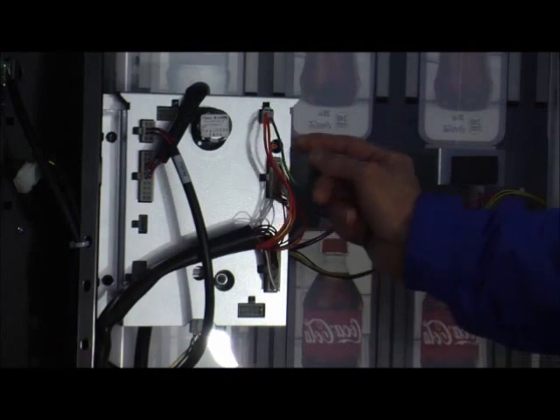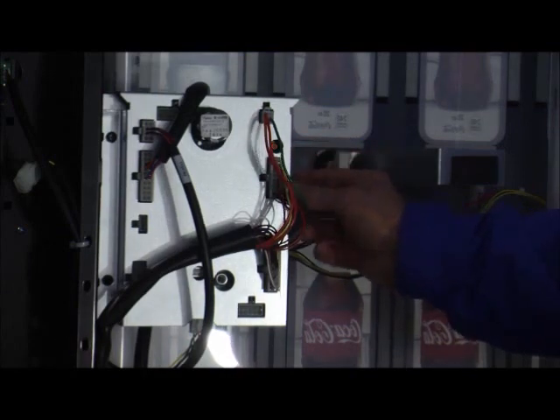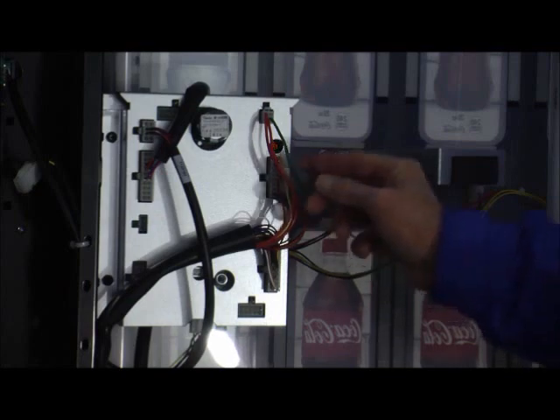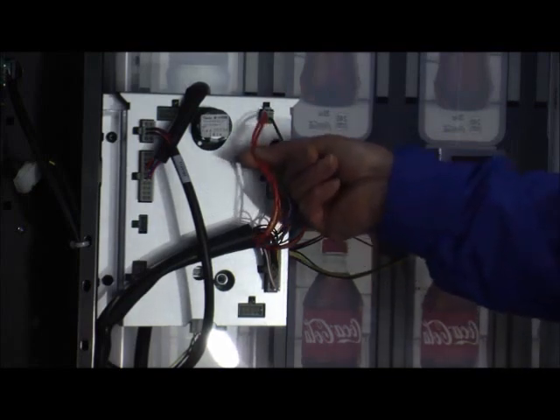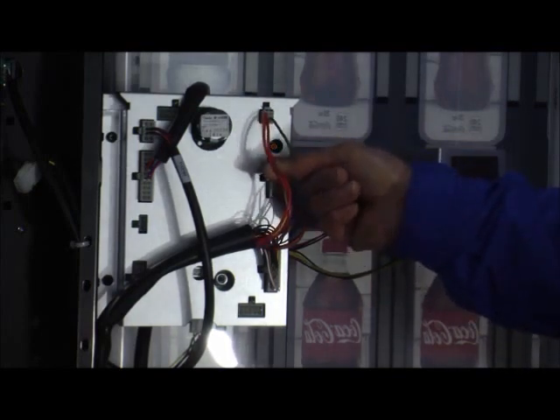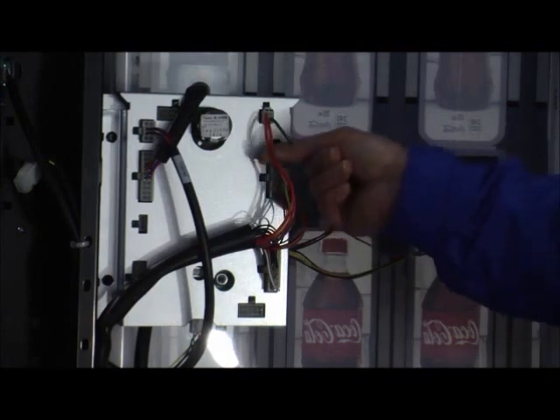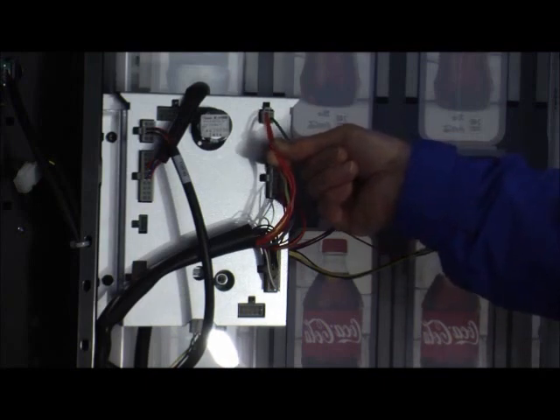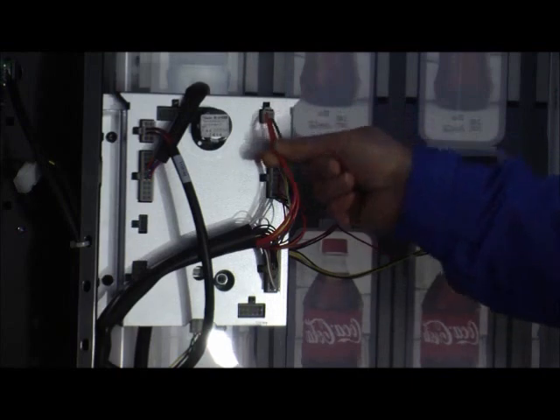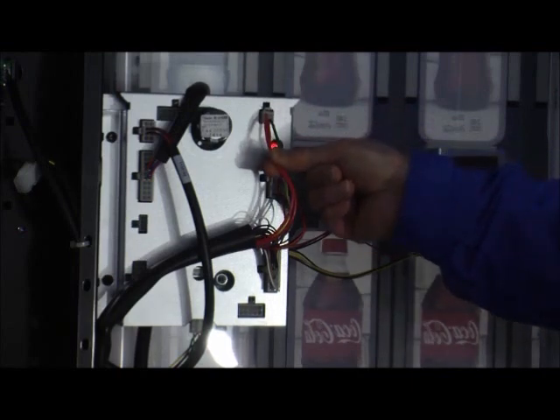If you have no light at all, that could indicate a bad control board or no power to the control board. So you would trace the power back down through your 24-volt transformer. The plug with the 2 orange wires right here, the 2 orange wires are coming from your 24-volt transformer, supplying power to the board. If you were to check these 2 orange wires, you should have 24 volts AC on these 2 orange wires. This is also a place that you can unplug power from the machines.